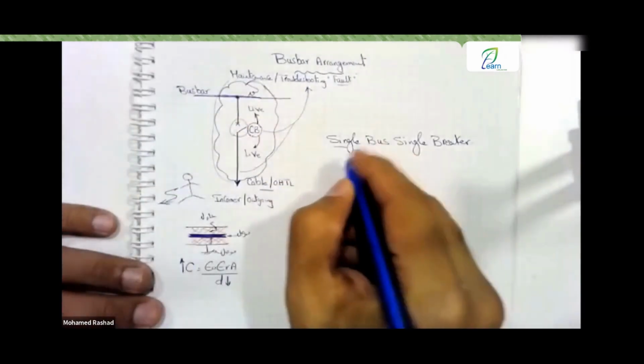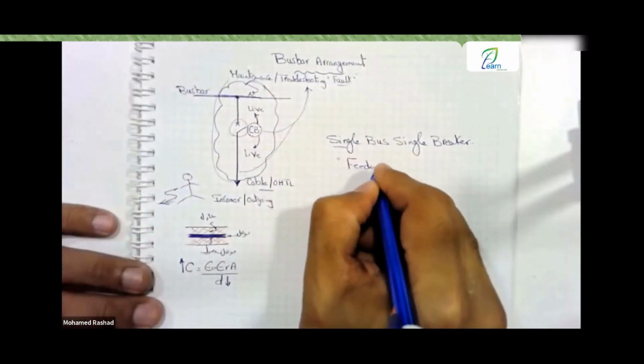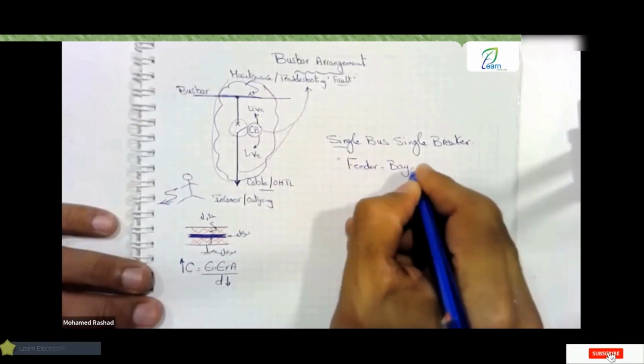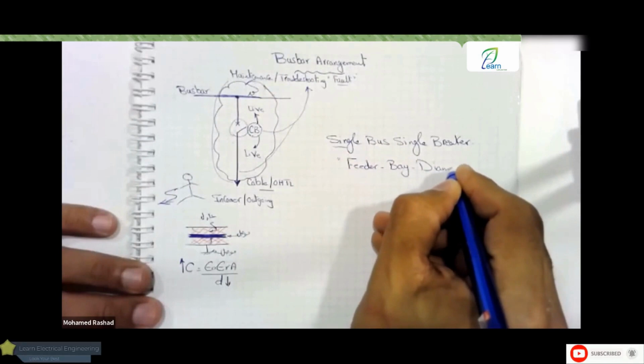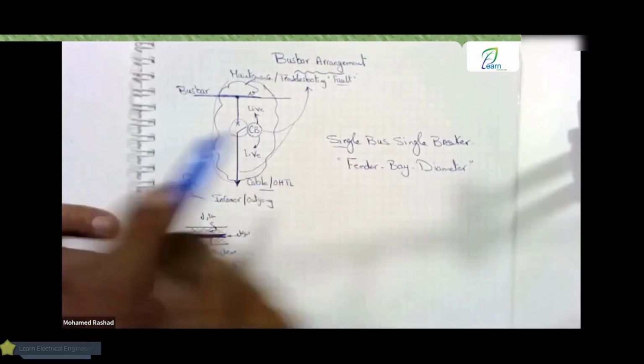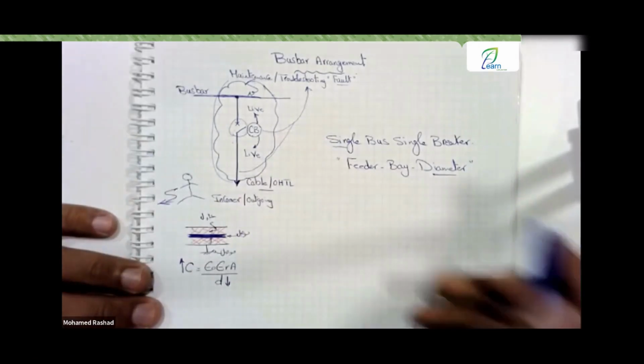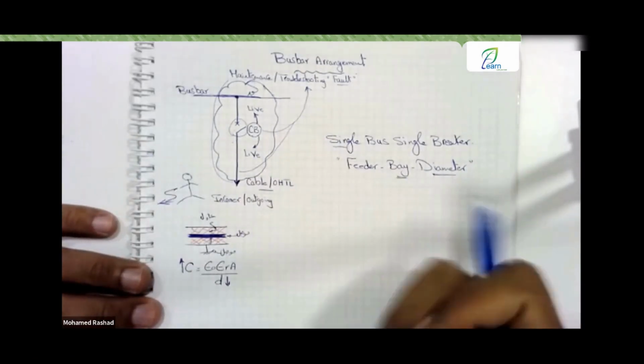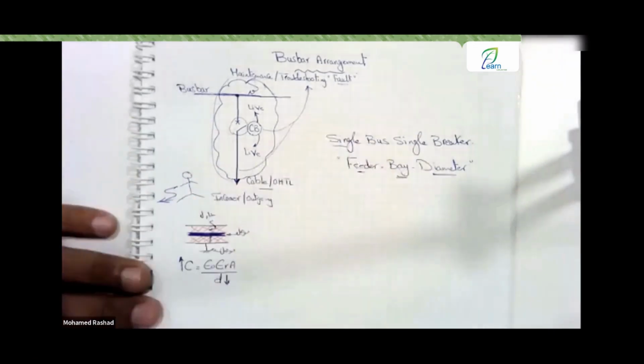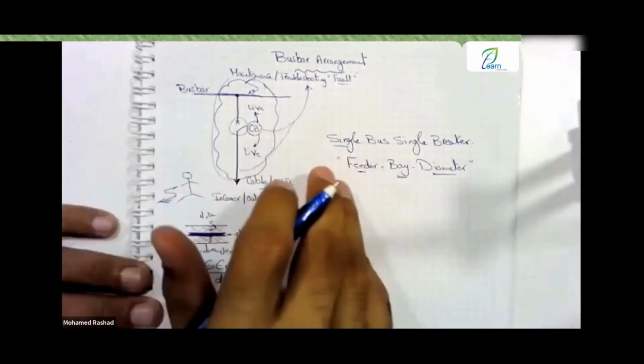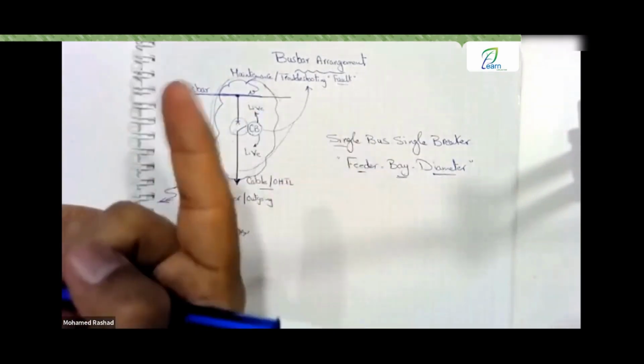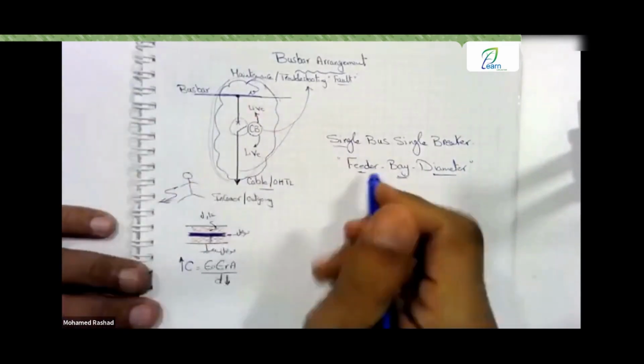This setup, guys, is referred to as a feeder, or it is called a cell or a diameter, any of these names. Of course, people working at the electricity company might say this is a diameter for us at 380 kV, and this is for us at 132, 110, or 115, which is the high voltage, and the feeder is for us in the medium voltage. I'm telling you, you can call these three terms whatever you want. So this setup is called a feeder, regardless of whether the feeder supplies a bus bar or a load, it's called a feeder, or a cell, or a diameter, that's fine, any name from those terms.